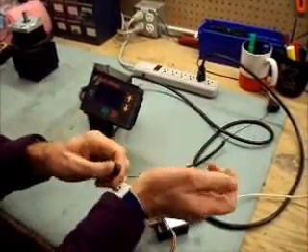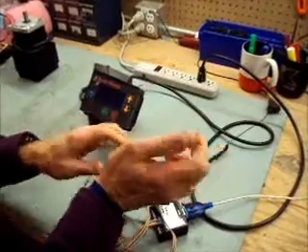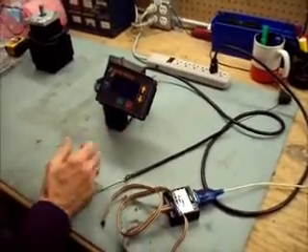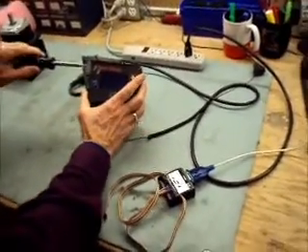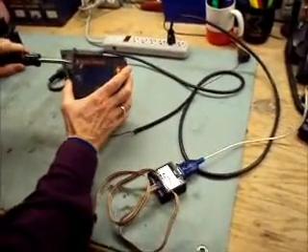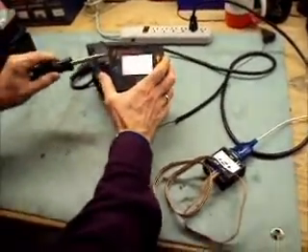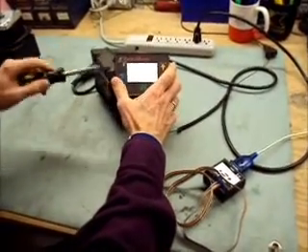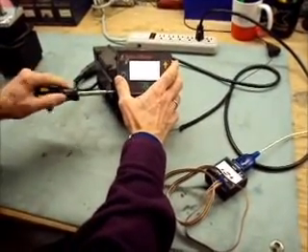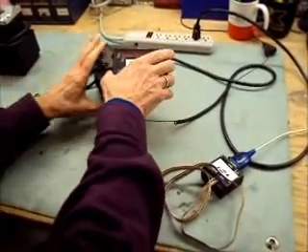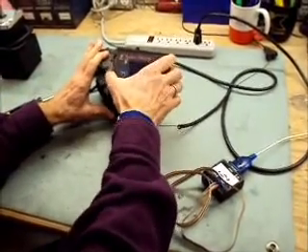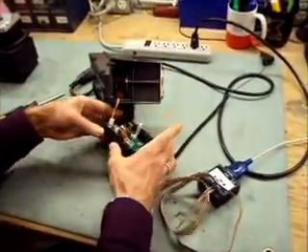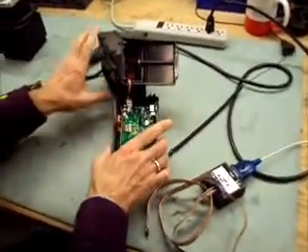I'm going to use an ESD strap because I'm going to be touching some of the electronics inside, and that's the preferred method. So you can open up the display head, rotate it around.